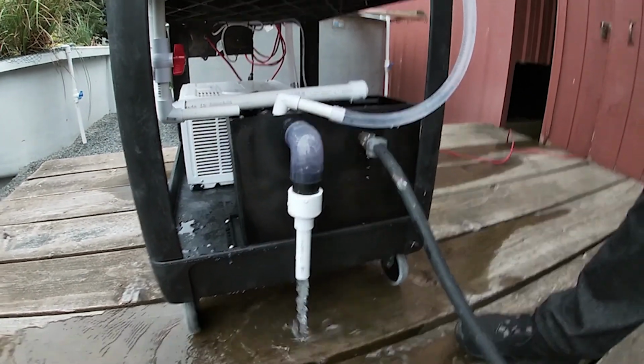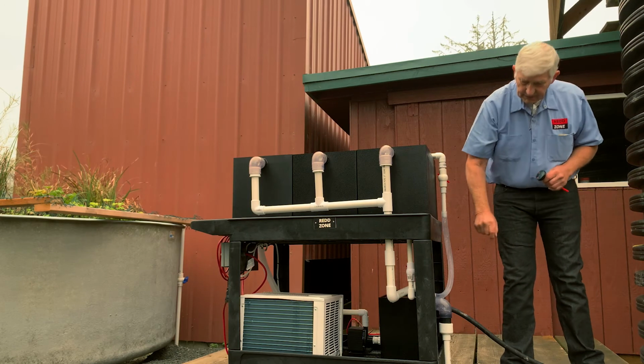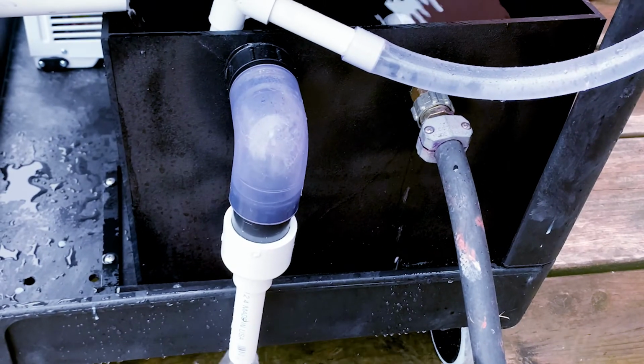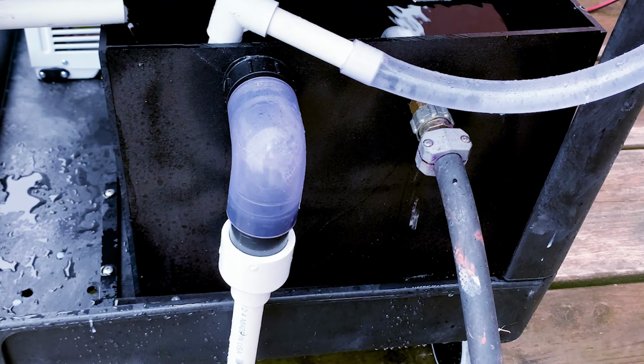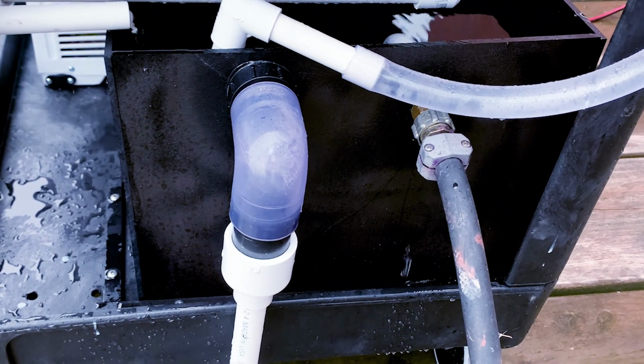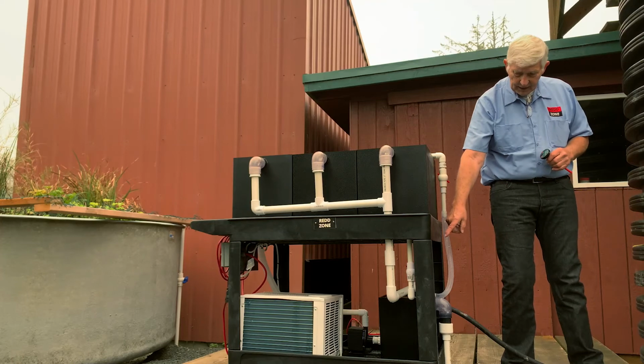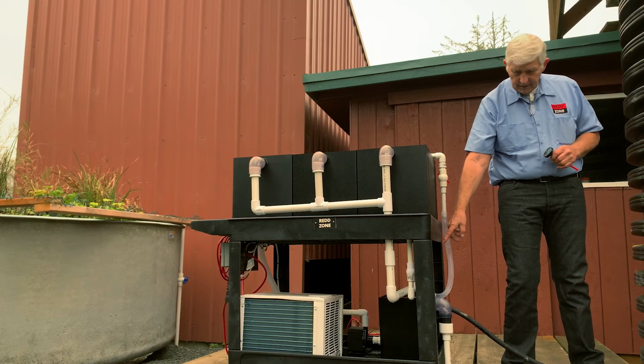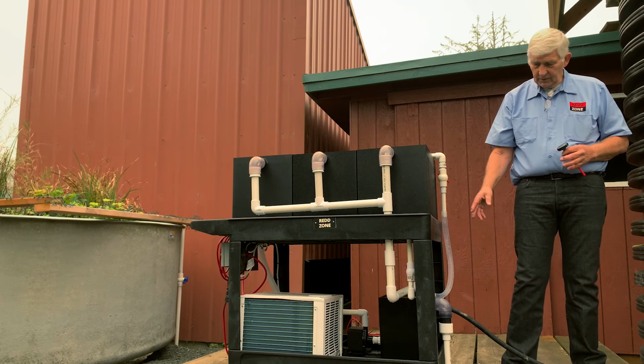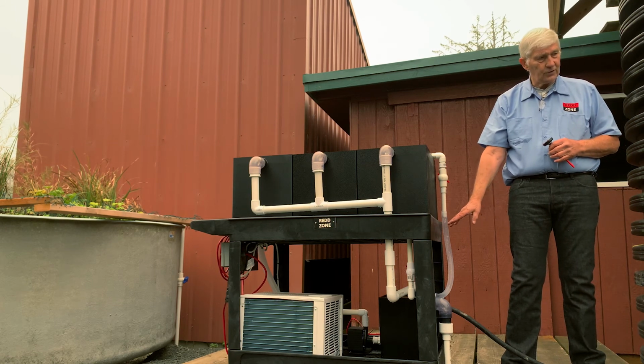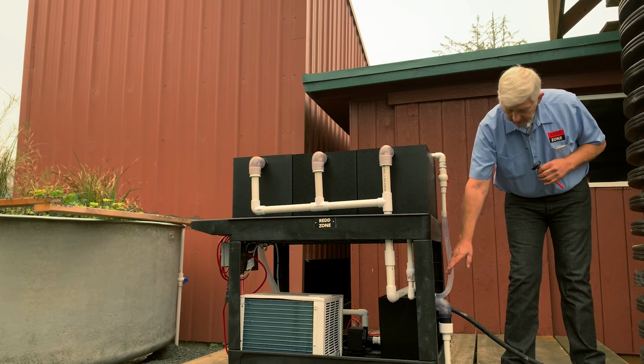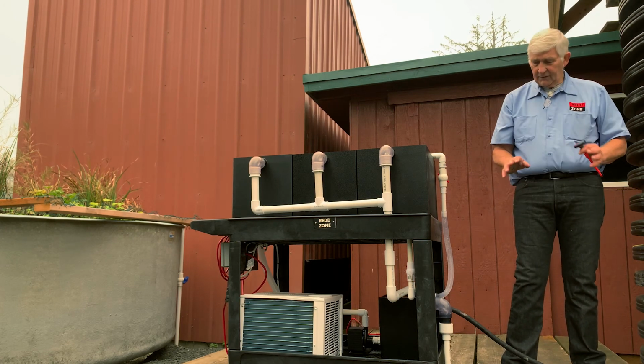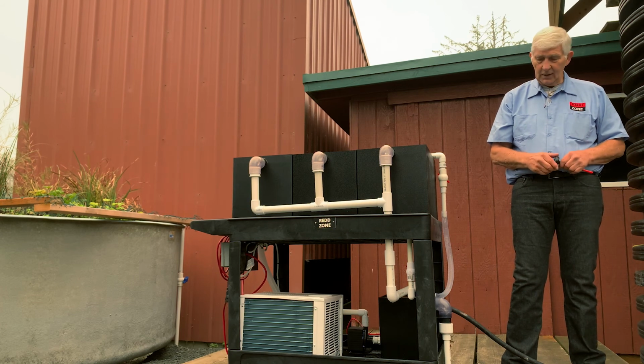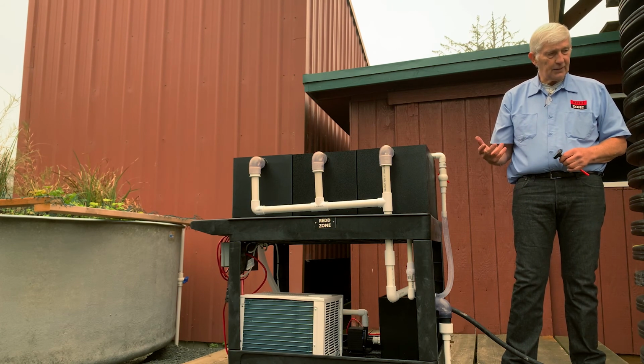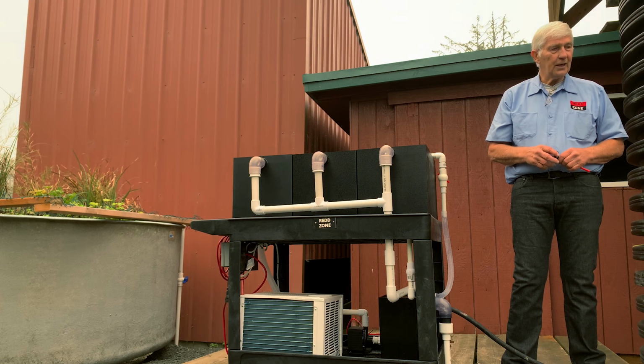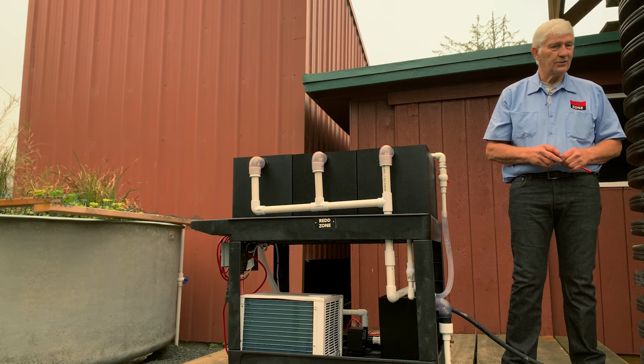Now the reason there's this second bypass is that it's below the pressure plate in the incubator box. So as the water gets down to the pressure plate, it'll continue to drain, but it'll drain into the reservoir, and the pump will not come on as long as that reservoir is filled, and it'll only go down to the bottom of the overflow. It'll never get low enough for the automatic refill to come on until the pump starts up again, and usually by then you're already there attending to whatever the emergency was.